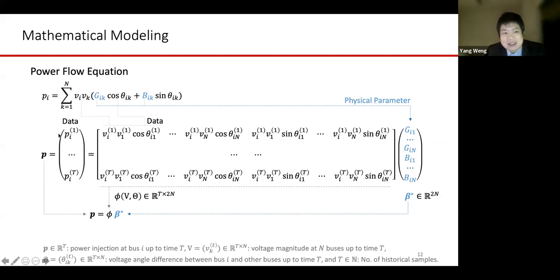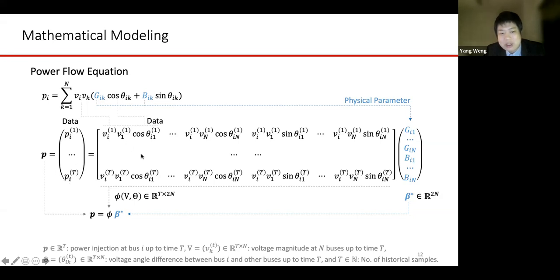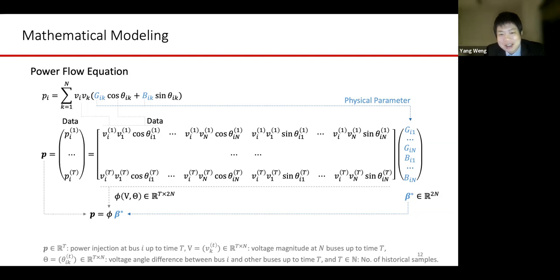Coming to the basics of power flow analysis: power injection is a summation of different flows. Looking at the topology, which is unknown in the Carnegie Mellon example, our goal is to learn the blue parts — the admittance parameters. Everything else, like voltage (measured by the system) and power (for billing), is data. So we know the power injection at different places and the voltage magnitude and phase angle, and the only thing we don't know is beta, which covers topology and parameters. This is linear — very good news. But the trouble is: do we really know the phase angle theta? Do we have micro-PMUs everywhere? Probably not. And do we have voltages all the time? Utilities sometimes only care about P for billing purposes.